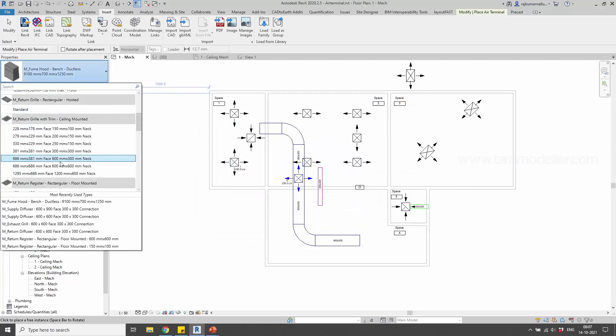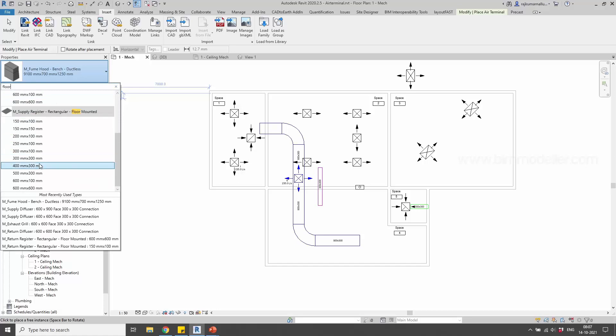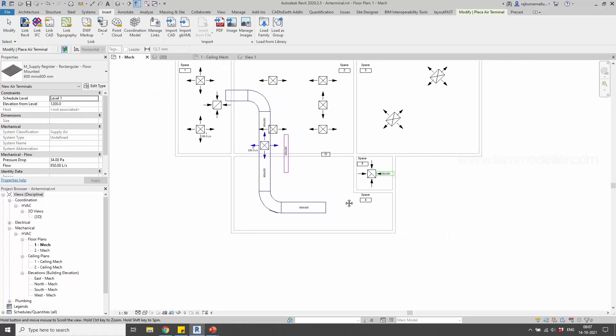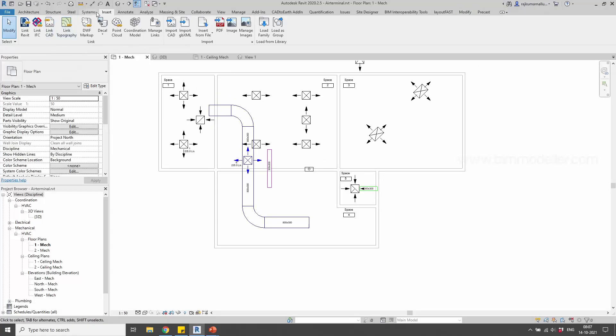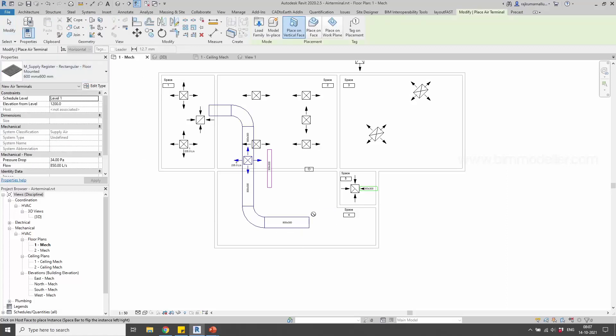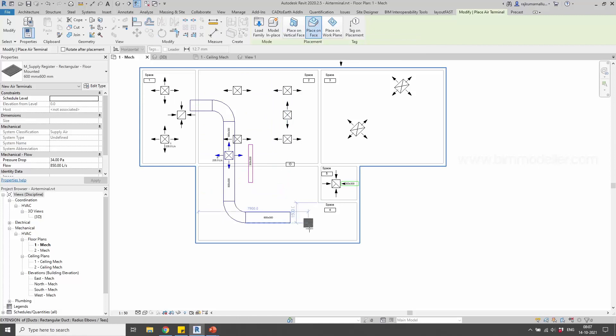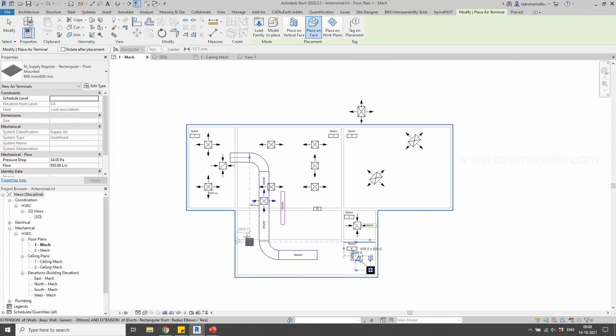Once it is loaded, you can select it. For example, I need to place a floor-based diffuser. If I type 'floor,' I get 'Floor Mounted Supply Register 600 by 600.' You'll have the option to place it on the floor or ceiling. Go to Air Terminal, select floor mount. It says 'Place on Vertical Face' — we don't want vertical face, we want floor face. Select it — the floor will be highlighted. Wherever you need, in the corner of the room, you can place it as per your requirement.